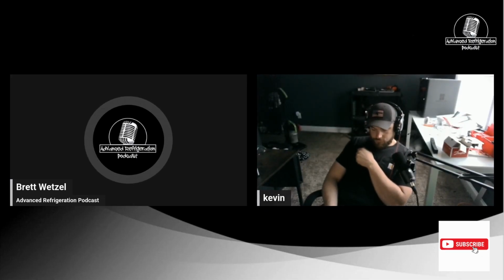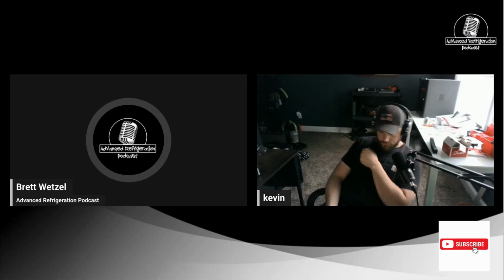So once we get all the superheats even, and once we have the fan stats set where they're supposed to be, I'm a firm believer that they need to be on the suction line. That way, for reverse flow, as soon as it gets that hot gas load, it's going to kick the fans out instantly. I had the guys set it for, I think, 40 degrees, and then do a 20 degree differential. So the suction line essentially would have to get down to 20.